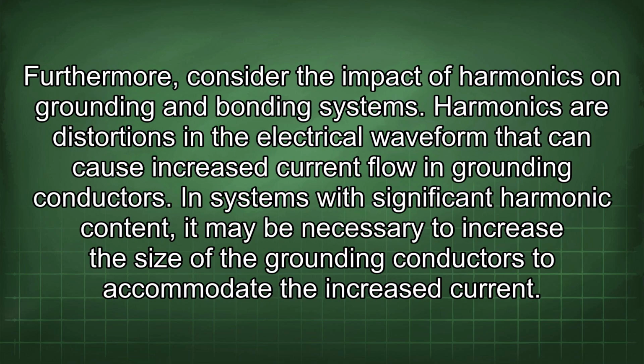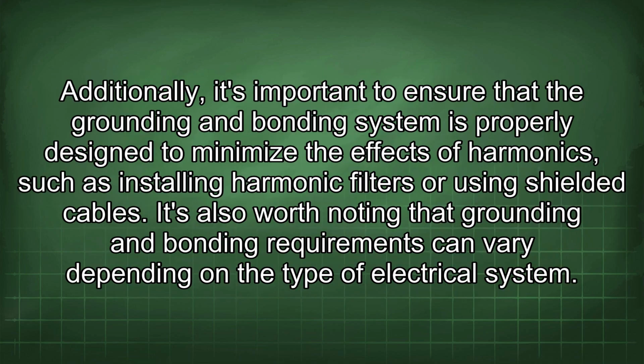Furthermore, consider the impact of harmonics on grounding and bonding systems. Harmonics are distortions in the electrical waveform that can cause increased current flow in grounding conductors. In systems with significant harmonic content, it may be necessary to increase the size of the grounding conductors to accommodate the increased current. Additionally, it's important to ensure that the grounding and bonding system is properly designed to minimize the effects of harmonics, such as installing harmonic filters or using shielded cables.